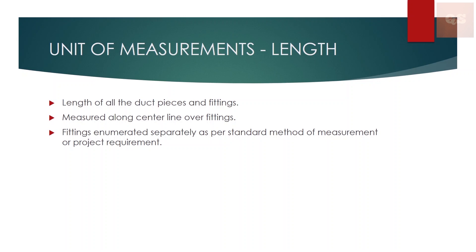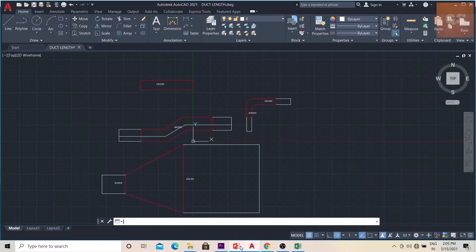If it is required that fittings need to be enumerated separately, only the length of the rectangular pieces are taken and the fittings are separately counted. But if the requirement is that fittings also need to be included within the linear measurement, then the measurement is taken over the center line over the fittings.